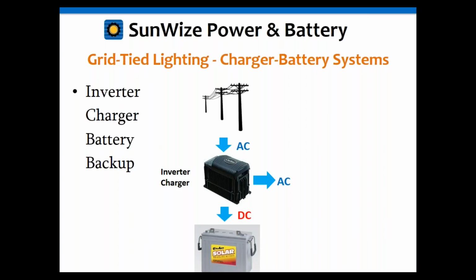current to charge the battery, and then also AC power directly to the load. And then what happens is it has an automatic transfer switch in there, such that when it loses utility power, it will transfer from the utility to the internal inverter itself, to what they call invert mode. The problem with that is there can be a slight lag or delay, and that may cause the light to blip. That may or may not be a problem. If you have sophisticated controls in the lighting, that may take time to reboot, may be a problem, especially in a critical load situation when it comes to obstruction lighting and tower lighting and stuff like that. If you have an airplane up in the air, having it down for 10, 15, 20 seconds while it reboots itself may not be a good thing. So you may want to keep that in mind.